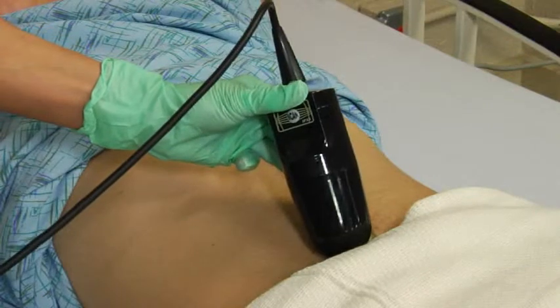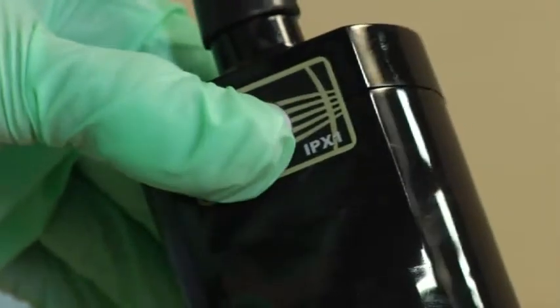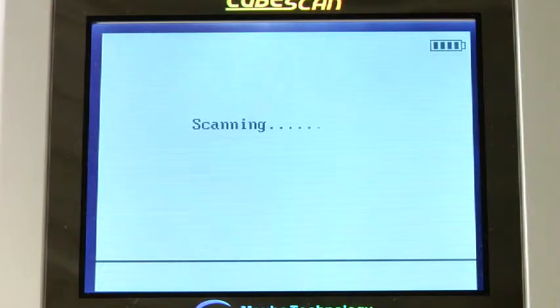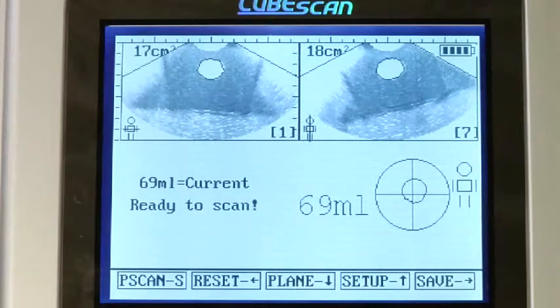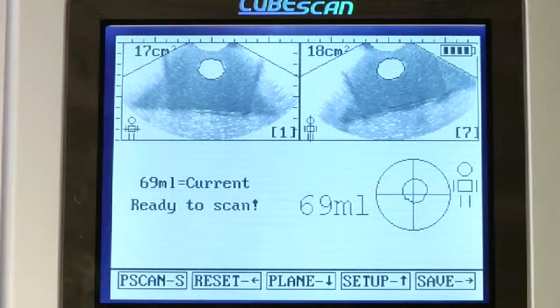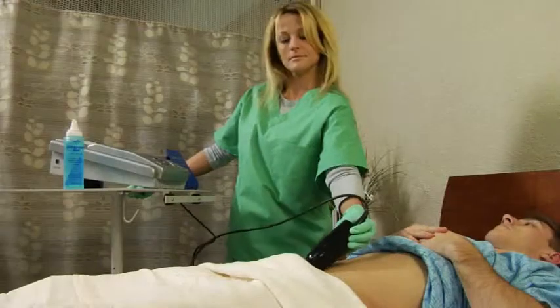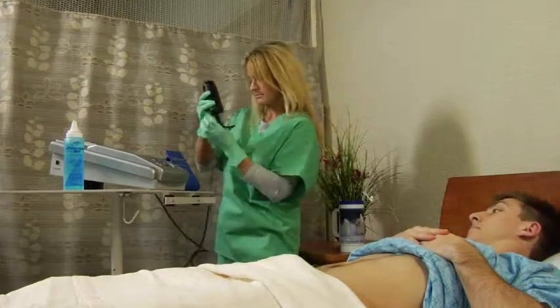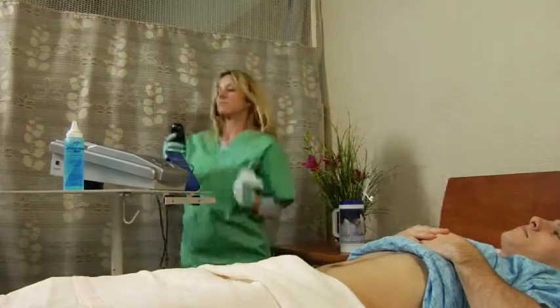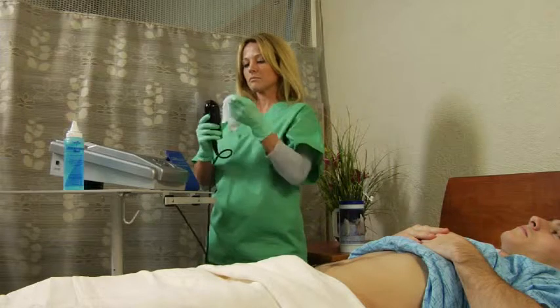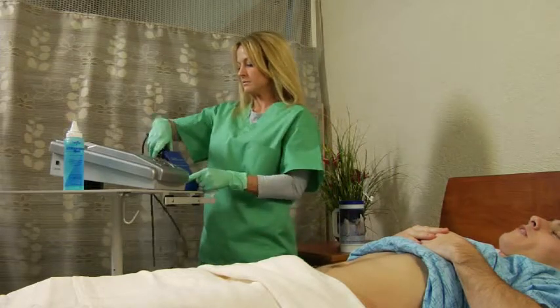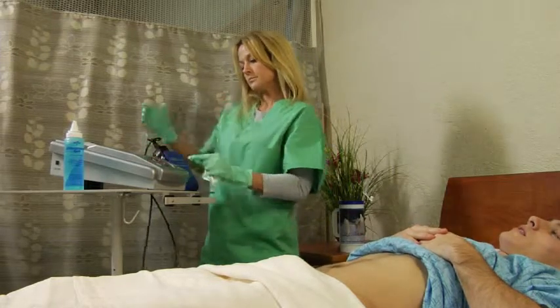Once you have the probe positioned in the optimal location, press the scan button again. The screen will read, "Scanning." During this time, do not lift or remove the probe. In a few short seconds, the screen will show the ultrasound pictures and the volume in milliliters will be large and apparent. When the scan is complete, and the ultrasound pictures and volume measurement appear on the screen, clean the probe and place it back in the holster. Please refer to the user's manual for recommended cleaning solutions.